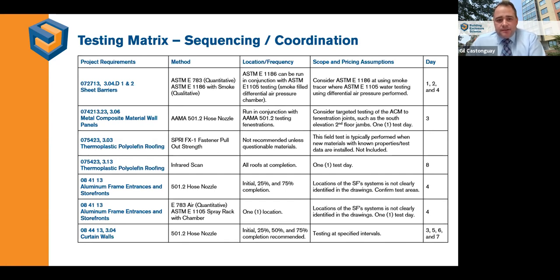So in our testing matrix, we've started coordinating multiple types of testing in a single test day if we can. That's been a big development, because now we're able to get a lot more testing done in less time on site with fewer mobilizations. But it does take extra effort. You have to understand what goes into the test, and communicate with the construction manager to make sure they're ready for you to jump from a chamber test in the morning to hanging off a lift doing a hose nozzle test in the afternoon. But it does help save on mobilizations.